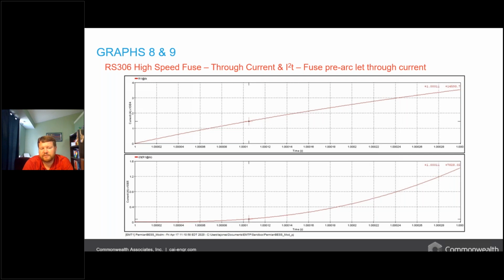So current limiting fuses are very, very understood when it comes to AC systems. The time constant of AC systems is very well understood. We can measure this. We can apply current limiting fuses to most 60 hertz systems relatively easily with typical time current curves provided by the fuse manufacturers. However, that doesn't apply to DC systems, especially when we get into battery energy storage. So for battery energy storage, the time constant of the DC circuit is entirely dependent on the RLC of the DC collector system. And it's all one big circuit with all the different series batteries as sources. In this case, we had 52 sources feeding into this inverter. So it can be a very challenging and detailed operation to look at this.